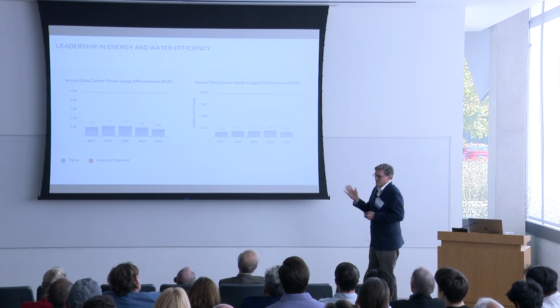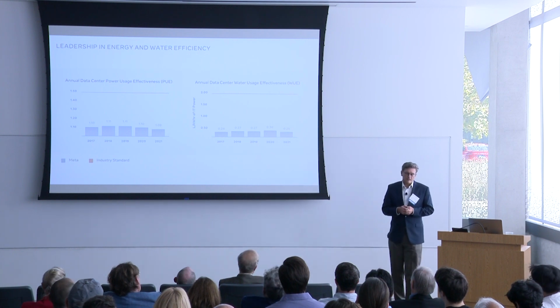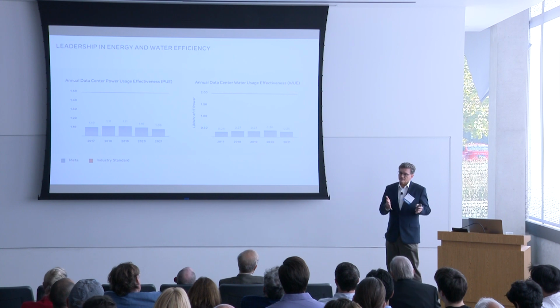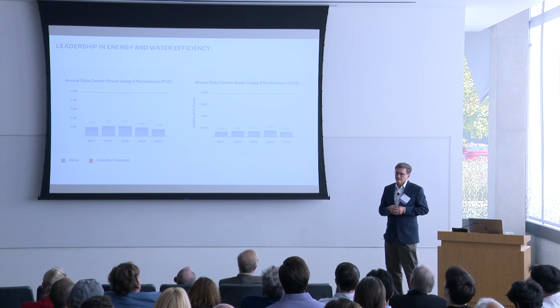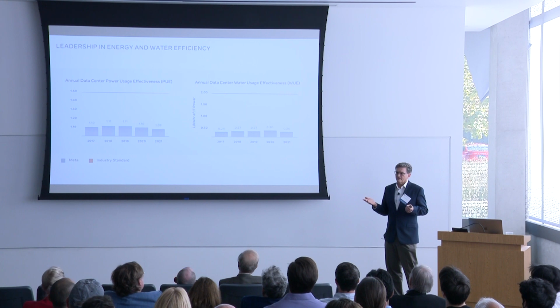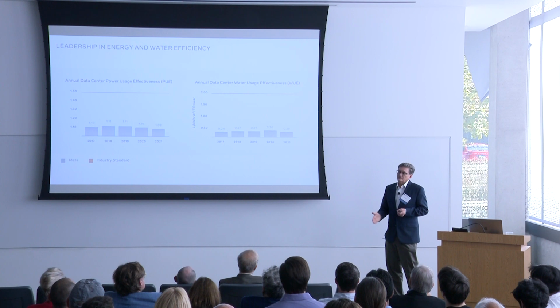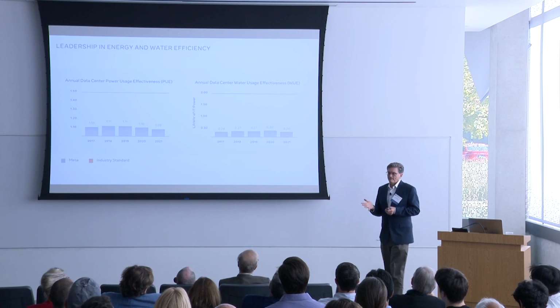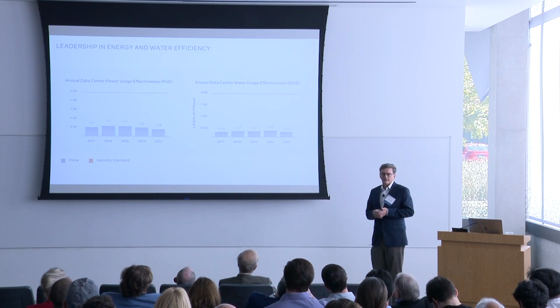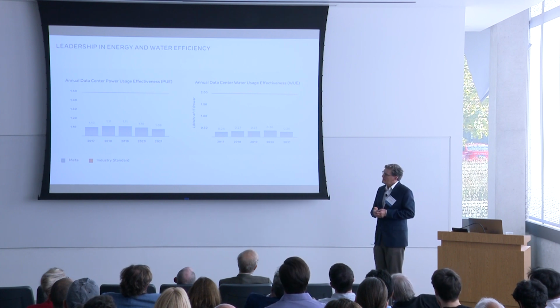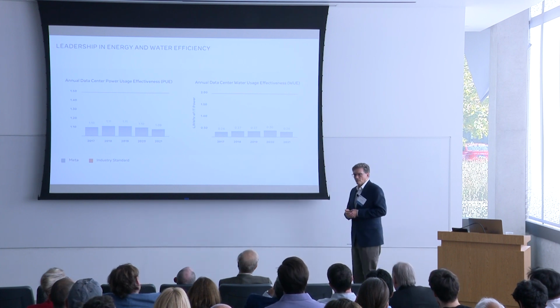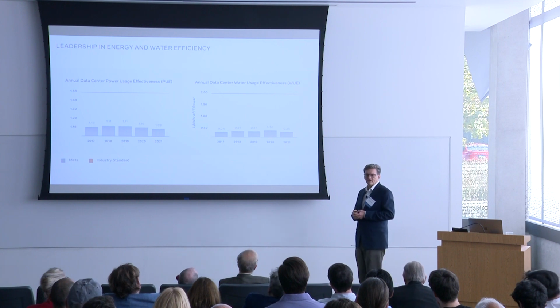Introducing that metric actually had a really profound effect on the focus on energy efficiency across that whole stack. At the same time, the emergence of hyperscalers made it quite easy, because we have full visibility into the cost and efficiency at all the layers, and it hits our bottom line. So there was a strong motive to fix this. We've seen what used to be a PUE of 2 not that long ago is now 1.5-ish or so, and we've been hovering in the 1.1 range for the last 5 or 6 years. Similar results from the other hyperscalers.